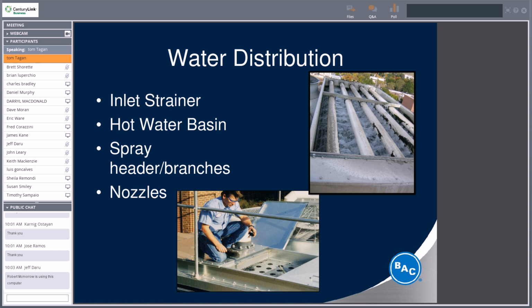So as you can see here, the water distribution, we're talking about the inlet strainer. You always want to keep that clean if there is one there. Hot water basin, you want to make sure that your water depths, as you can see to the upper right, that is a centrifugal fan cooling tower with a pressurized distribution spray header. That one looks pretty good. You can see an even distribution over the fill or the coil. I believe that's a coil product.